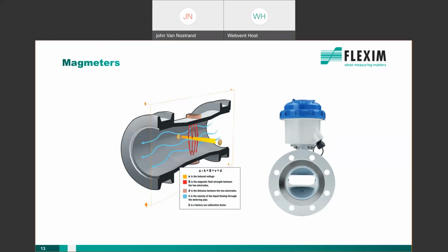The two electrodes must be completely isolated from the process by means of a liner, and the meter must be grounded to the earth with steel rings, cable, and grounding rods, etc., especially if there's any plastic piping. Like all flow meters, the pipe must remain full of liquid. The pipe size reduction that you see here is very common for magmeters because they want to increase the velocity through the meter. This also increases pressure drop and can increase pumping cost. We're going to talk a little bit more about that in a moment.